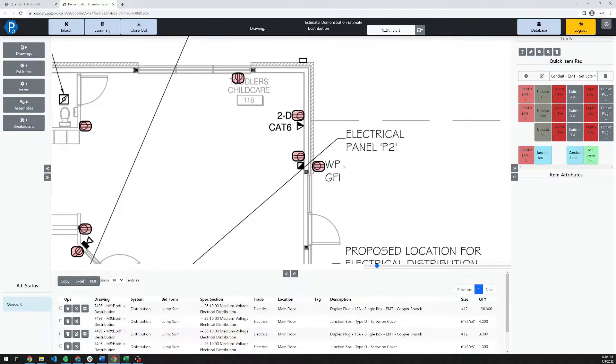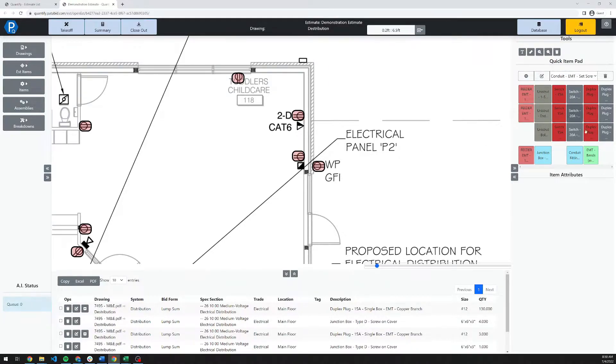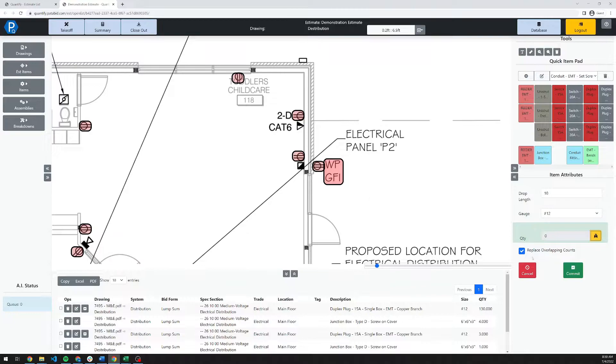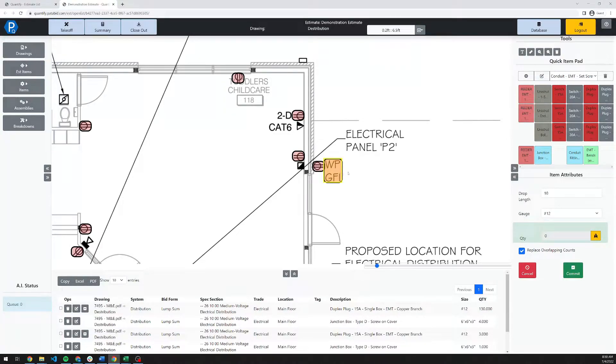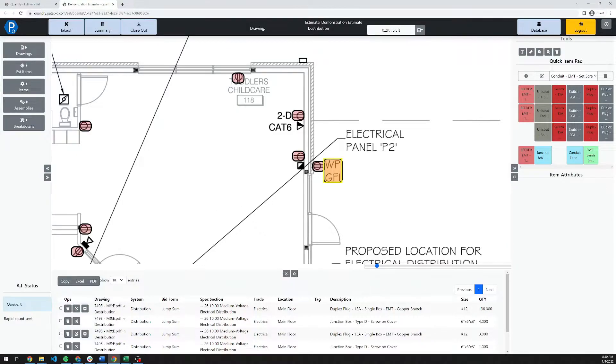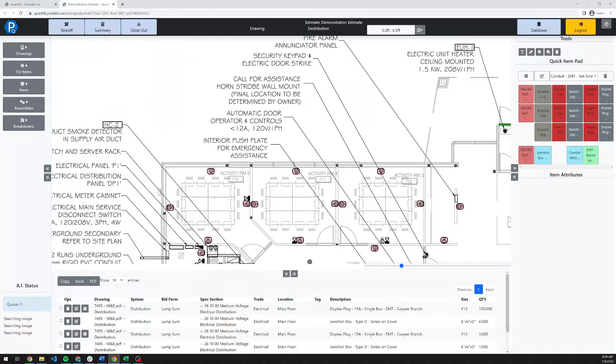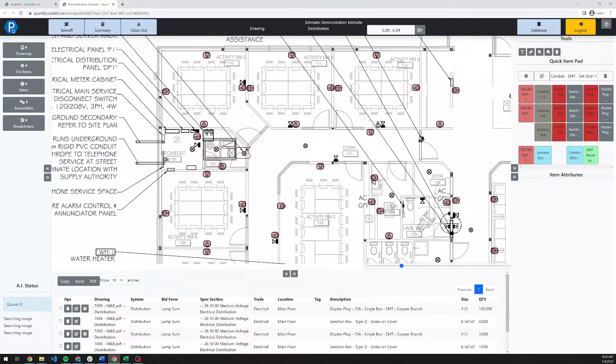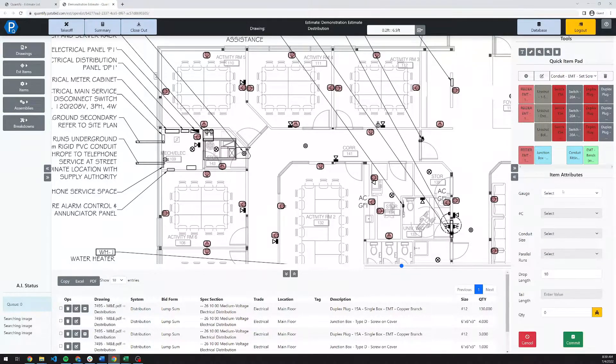Now that I have these plugs in, one of the notes on this drawing, the designer used the same symbol for all plugs, and then applied tags to differentiate. For example, this is a waterproof GFI. What we can do here is we can actually rerun the count. I'll select the robot again, and I will highlight the tag. We have this checkbox here, replace overlapping counts. Essentially what that does is the system is going to search the drawing for this tag, and anywhere where it overlaps a plug, it's going to replace that plug with the new GFI style plug. I'm going to hit commit and send that over. While that's now searching and updating my drawing, we're going to take off a feeder here from this panel.